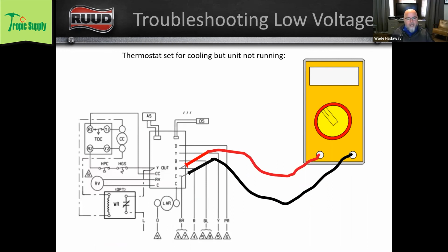All right, so now we have an outdoor unit that we're looking at. Thermostat is set for cooling. The outdoor unit's not running. We're going to go outside with our meter, and we're going to look to see, do we have power to our board, right? So we have 24 volts from our 24-volt red to common. So that's 24-volt hot to 24-volt common. We got 24 volts there, so now we're getting voltage at our board.